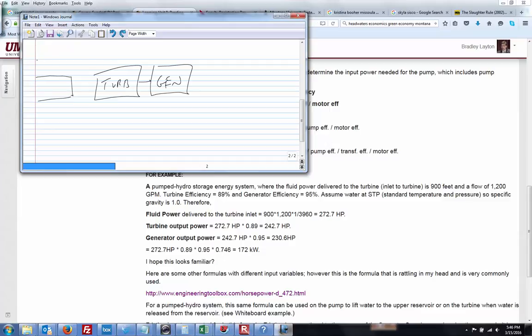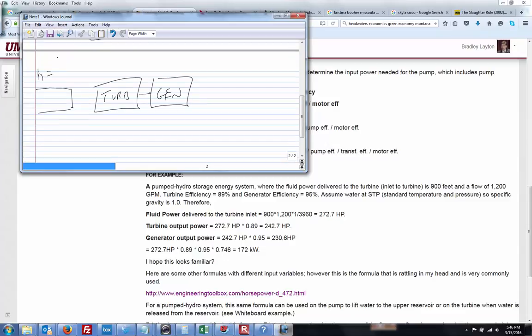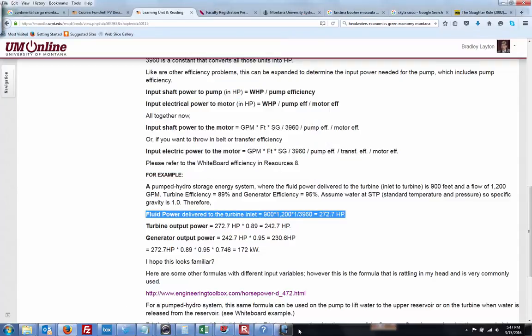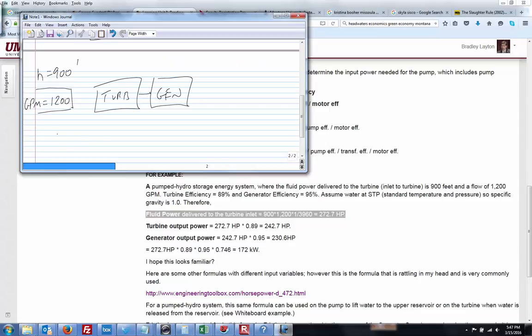So we use P for power. So I'll just write the head equals 900 feet. The GPM, gallons per minute, GPM equals 1200. Okay, so 900 times 1200 times 1. So fluid, I'll just write this as fluid power equals 900 times 1200 times 1 divided by 3960. And I'm going to trust the math on this and say that equals 272.7. Actually, let's just run it.